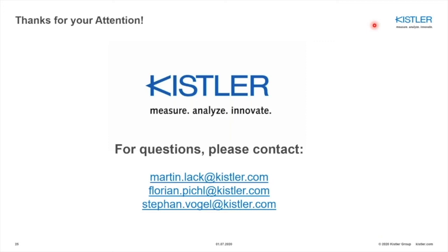For Martin: does the Kistler product fulfill FDA 21 CFR Part 11, or GMP Europe Annex 11? Yes, both devices, the ComoNeo and the Maximus TL, have been checked by an external company regarding Part 11 compliance. With the latest firmware release, ComoNeo 4.0 and Maximus TLML 1.7, we already solved some tasks so our customers can implement and certify our devices more easily. The major topics of these software changes are the audit trail - each change in the device must be documented by the defined user, with time and date, so who changed what and when. The old value is required and the new value is also available in the audit trail.